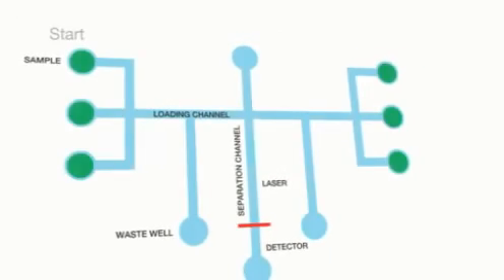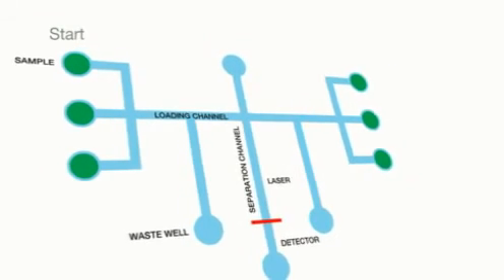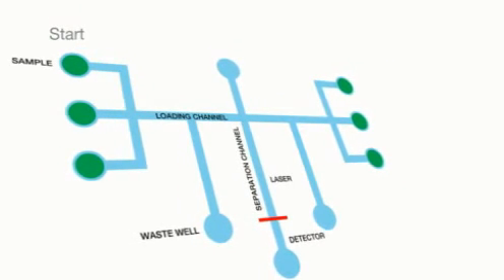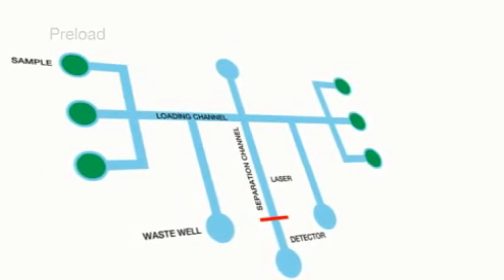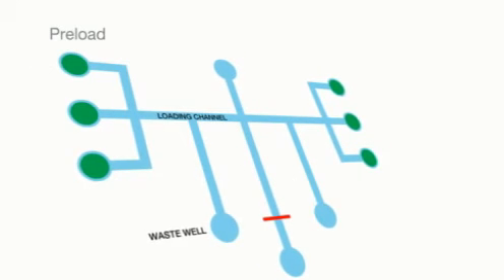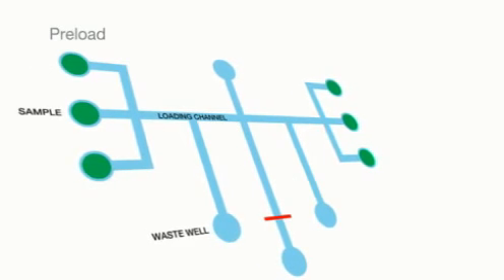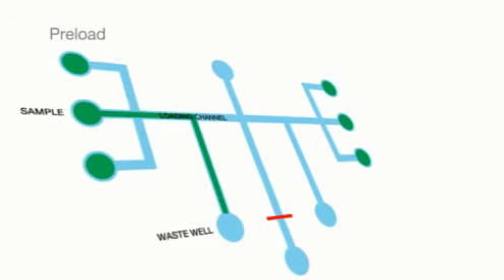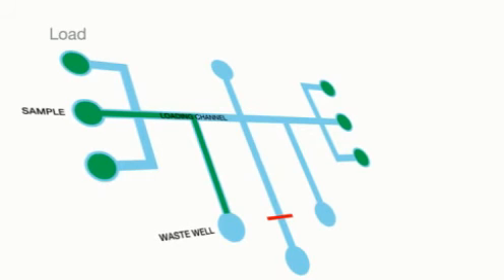The Experion analysis chip is a complex network of these wells and microchannels. Within the chip, the process begins by controlling the current or voltage at the appropriate wells to move the sample into the loading channel, continuing past the separation channel intersection.